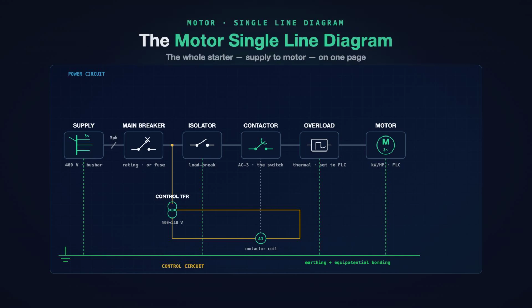This is a motor single-line diagram. The whole motor circuit drawn as one clean line from the incoming supply all the way to the motor itself. If you have ever sized a motor feeder, built a starter panel, or booked an inspection, this is the drawing at the center of it. One page, the whole starter chain, every protection device, the way the power actually flows.